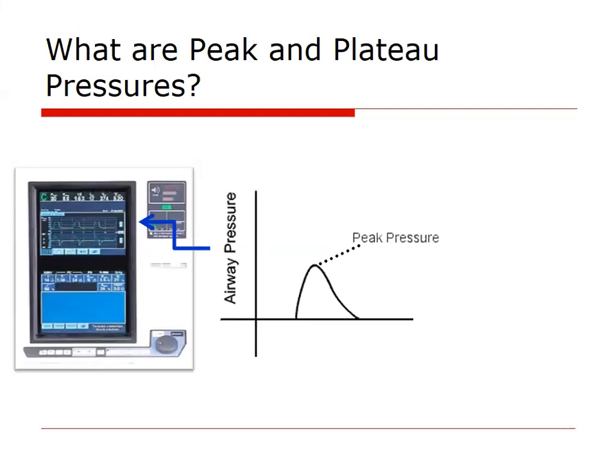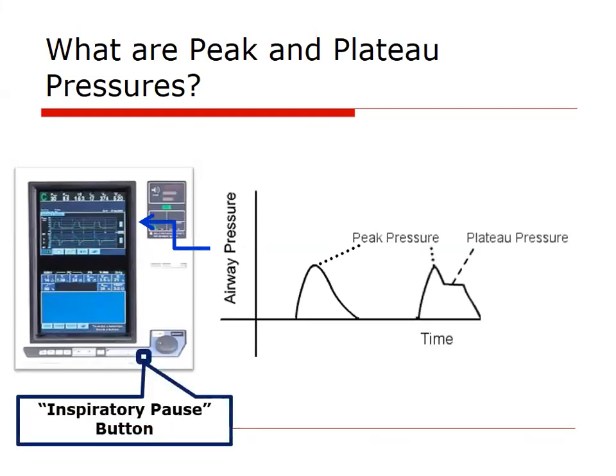If you press the inspiratory pause button, on the next breath, and just that one breath, the machine pushes the breath in but pauses for a second, closing the valves while the breath is in the patient before letting it out. So the pressure goes up to the peak pressure, then drops to this pause pressure that looks like a plateau. So it's called both an inspiratory pause or a plateau pressure. Then the breath goes out.